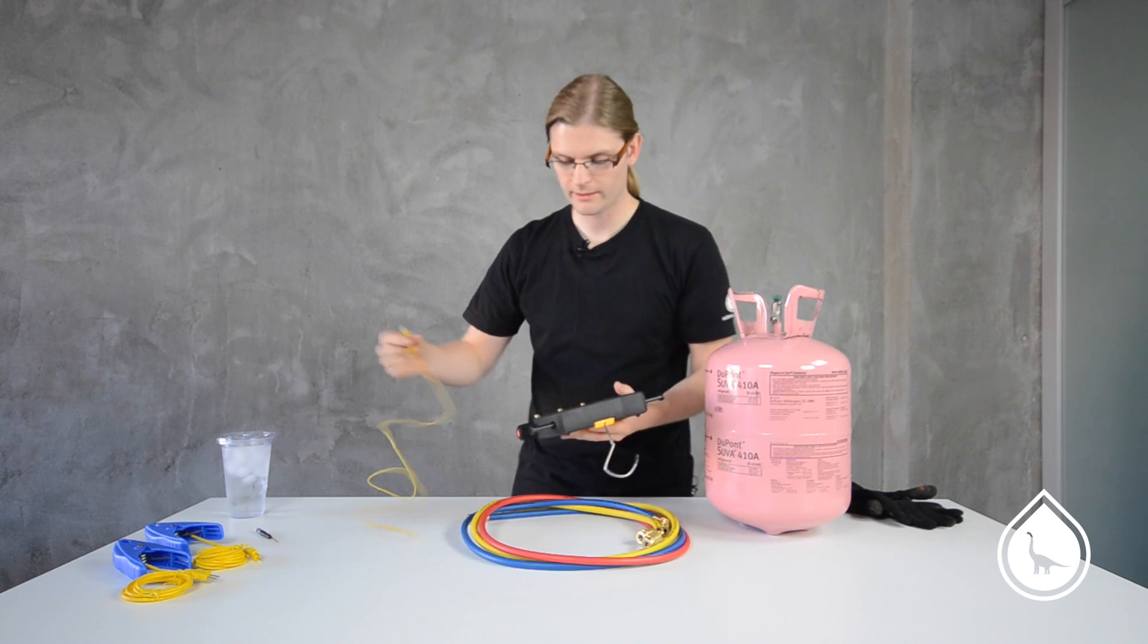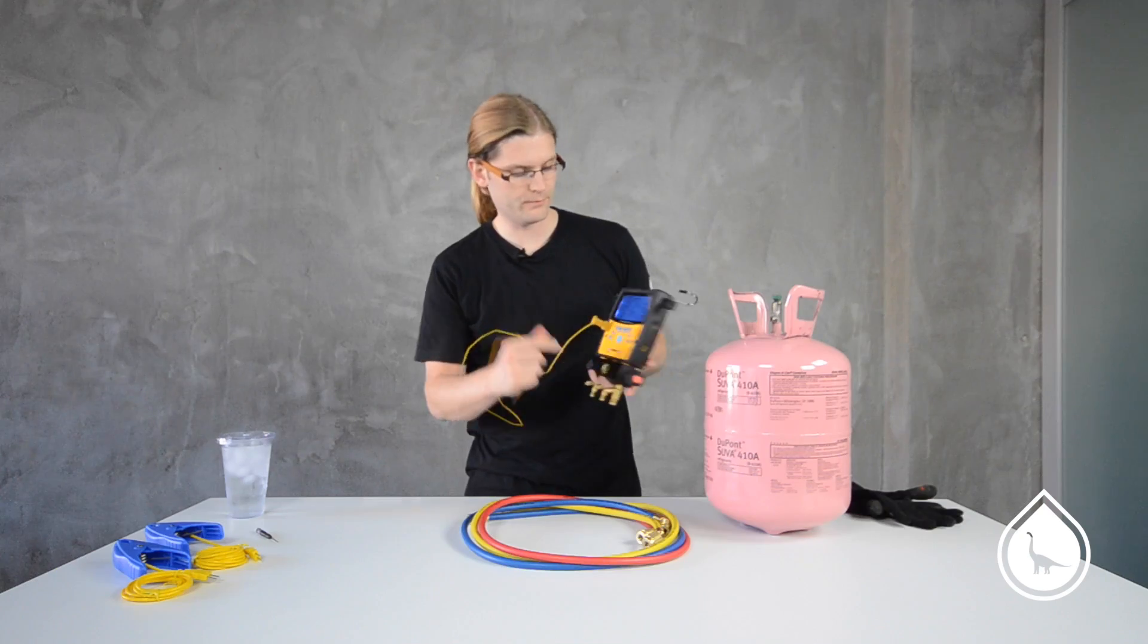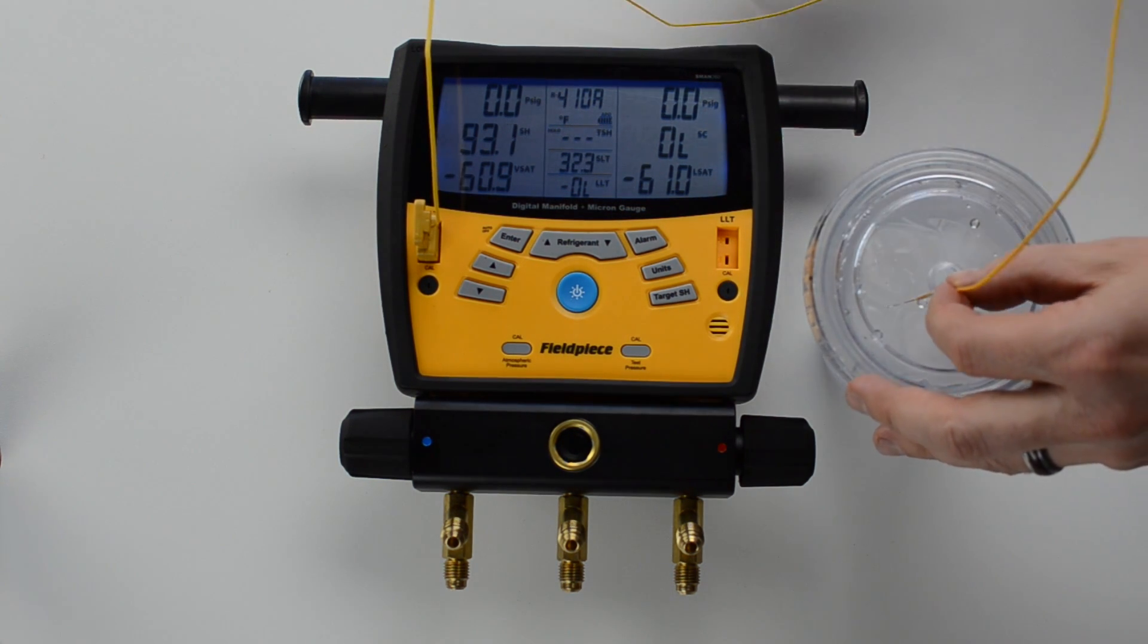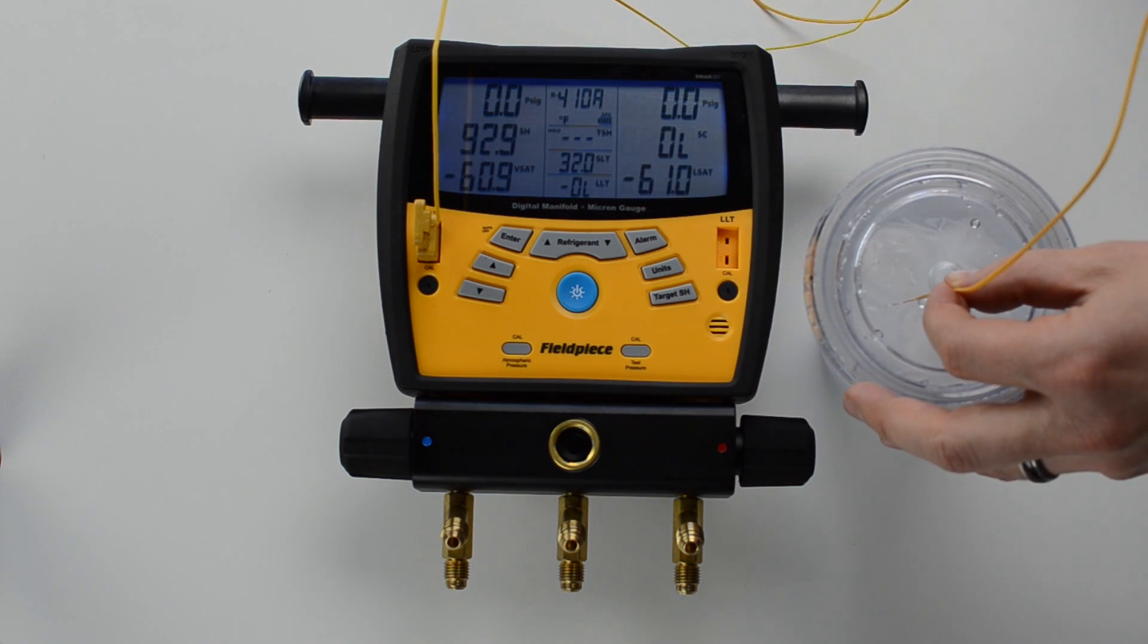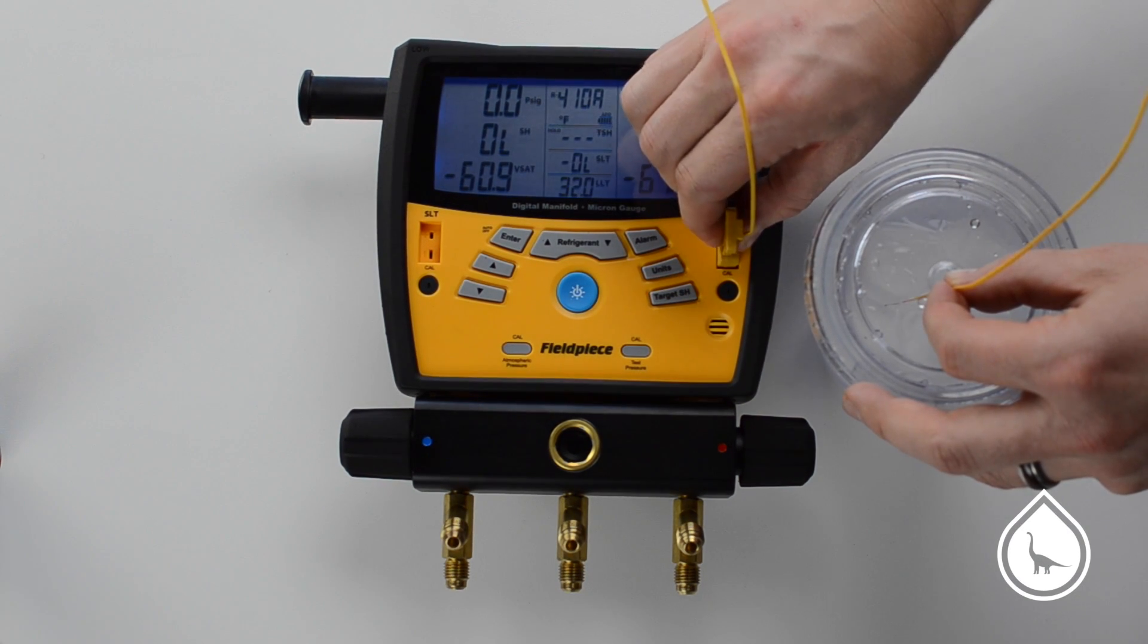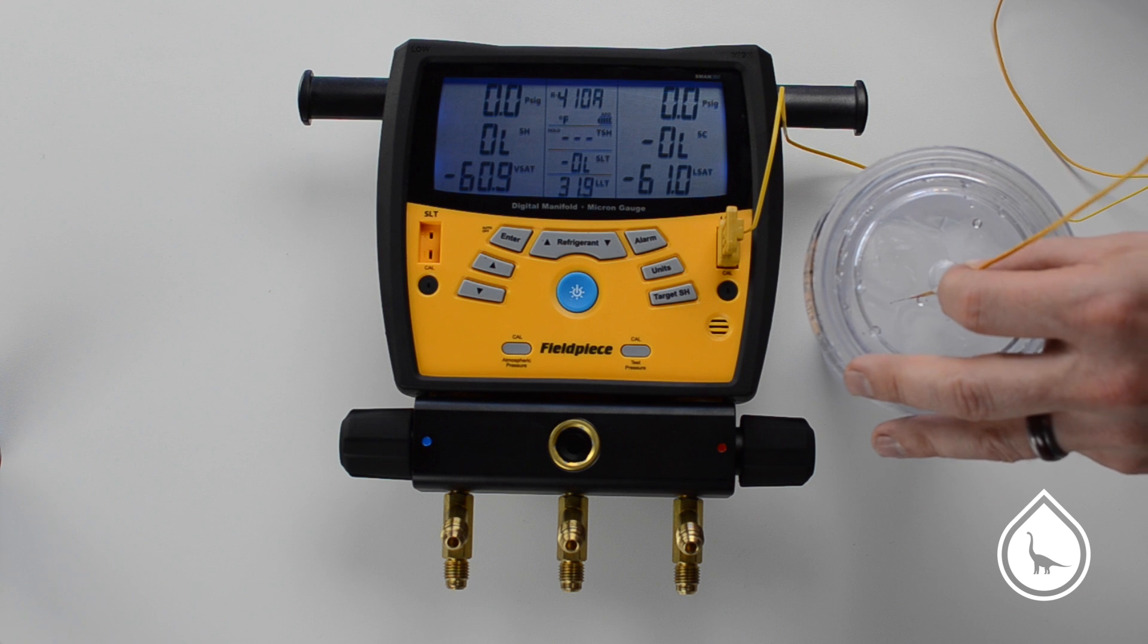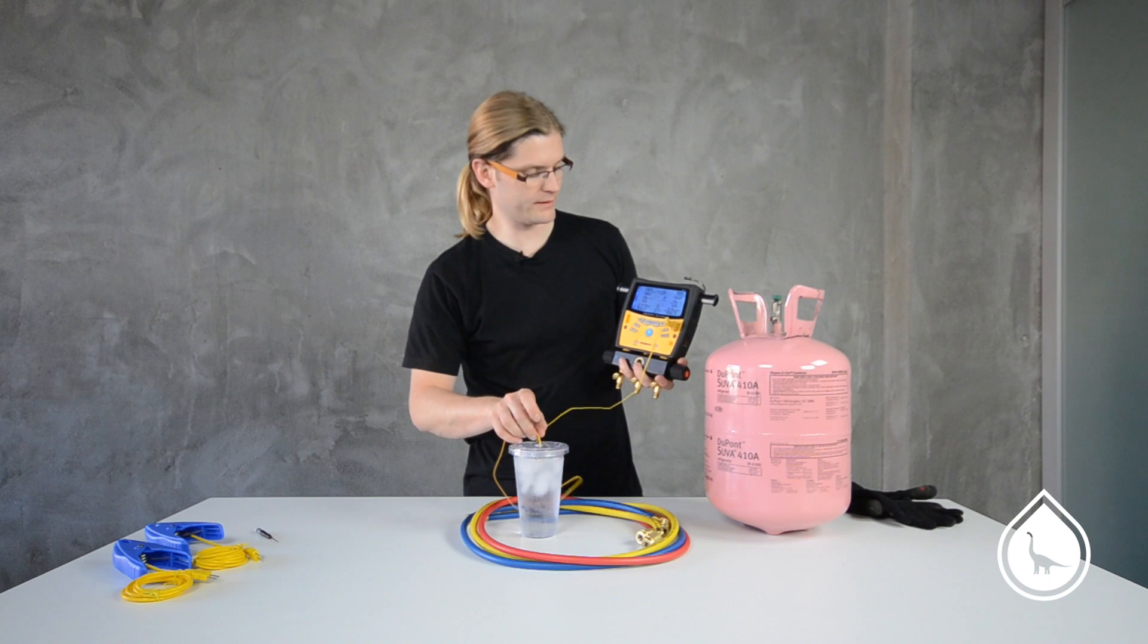Next thing we want to check is that the thermocouples are reading temperatures correctly. So I'm going to plug it into our suction line temperature port with the end of the thermocouple close to the ice, and I'm reading just over 32, 32.1. We'll plug into the liquid line temperature. We're reading 31.9, 32 right on. So I'm not going to touch those.